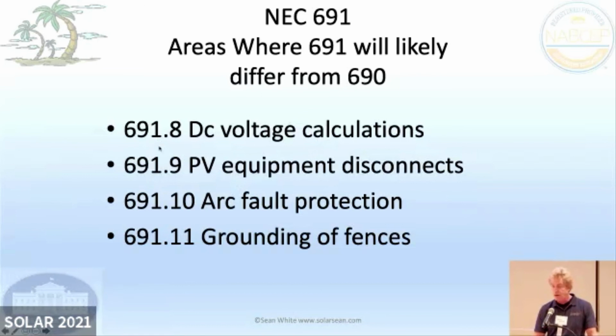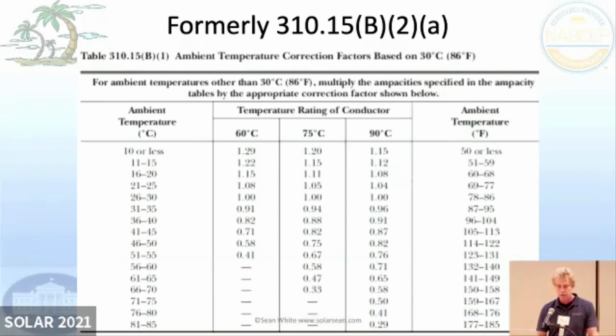So you can have different voltage calculations, even different current calculations, different PV equipment disconnects, so fewer disconnects. You have educated people in there, not just regular people walking around. You can get rid of your arc fault protection, which can save a lot of money. And also there are requirements for grounding of fences. So you've got that there. Here are some different things that they changed a little bit in the NEC that are kind of insignificant, but kind of confusing. Let me just show you.